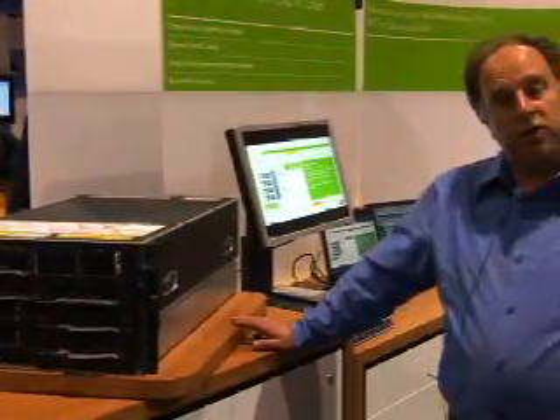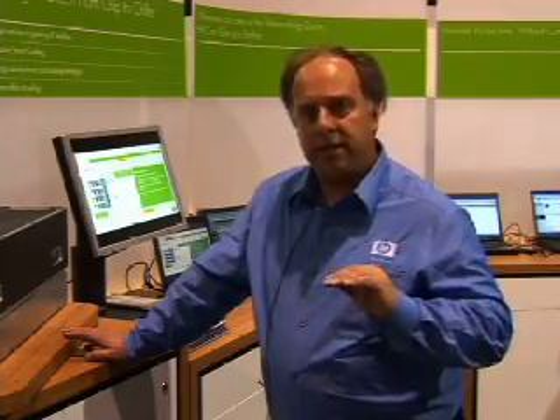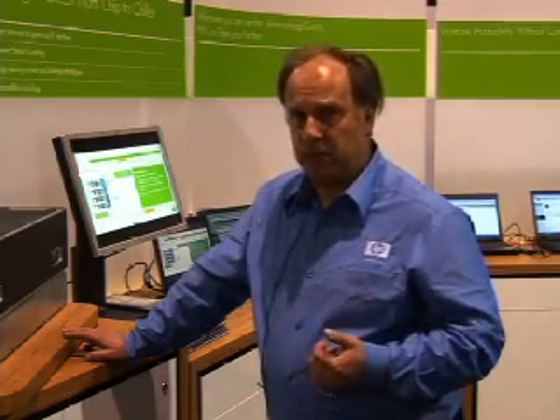When we look at our dynamic smart cooling capability, we put sensors throughout the data center that allow us to monitor where the heat is, and then we can actually change the airflow so that we're cooling those parts of the data center where it's getting hot because that's where the workloads are busiest. This allows us to keep the data center on average at a higher temperature, so we're not paying as much money to refrigerate and cool it. If you've ever been in a data center, you know it can be extremely cold in there. You don't have to do that as much when you use dynamic smart cooling.